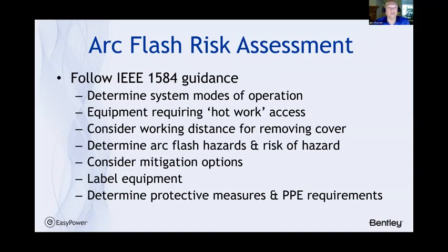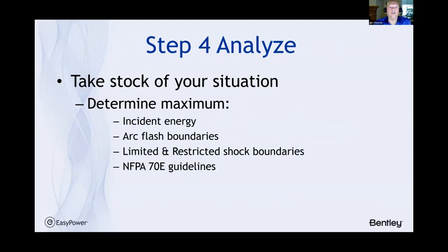But during the arc flash risk assessment, the tools can consider different working distances based upon whether or not you're going to have to do hot work or just observe it like you would on a thermal imaging. But in addition to labeling the equipment, you'd also determine the protective measures and the PPE requirements. And then once you've got these results, you need to really analyze and take stock of your situation. You need to really understand what equipment needs to be worked on, what can be processed, de-energized, and determine the maximum risk that you want to take as an organization, including the need to expose people to incident energy, the arc flash boundaries that will exist that could affect other workers in the area, and then the limited and restricted shock boundaries, which are going to be present once that cover is removed. And all this is per NFPA 70E guidelines.